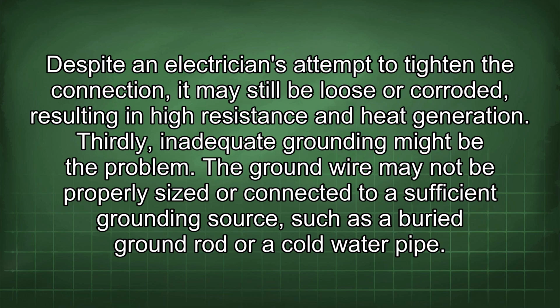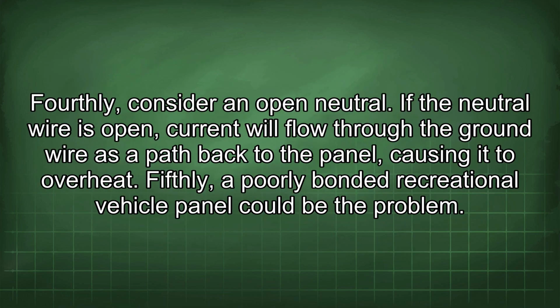heat generation. Thirdly, inadequate grounding might be the problem. The ground wire may not be properly sized or connected to a sufficient grounding source, such as a buried ground rod or a cold water pipe. Fourthly, consider an open neutral. If the neutral wire is open, current will flow through the ground wire as a path back to the panel, causing it to overheat. Fifthly, a poorly bonded recreational vehicle panel could be the problem.